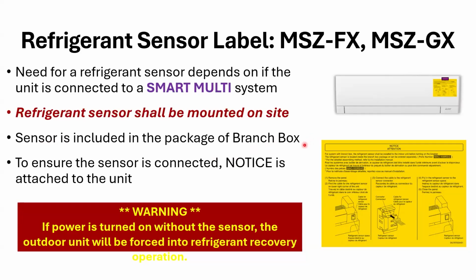There's some confusion about where the sensors are. With the smart multi, you have to have a branch box. In the branch box is where your sensors are located, packaged with the branch box. If you get a 3-port branch box, you're getting 3 sensors. If you get a 5-port branch box, you're getting 5 sensors. To ensure the sensor is connected, a notice is attached to the unit. Warning: if power is turned on without the sensor, the outdoor unit will be forced into refrigerant recovery mode. This is the label they're supposed to be putting on the units.